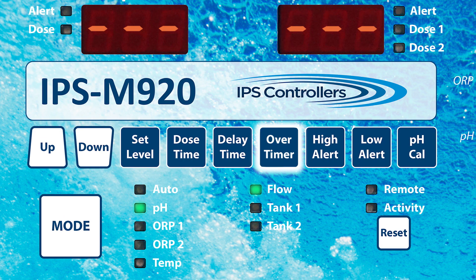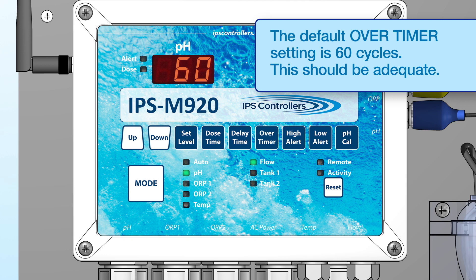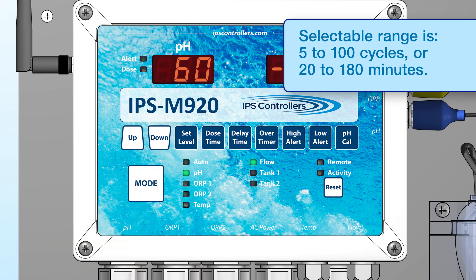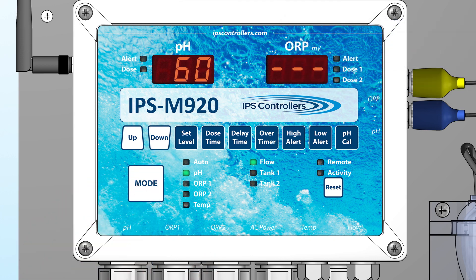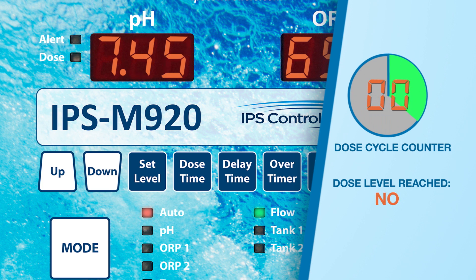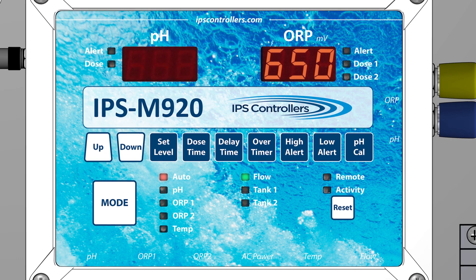The Over Timer is a safety mechanism. Press the Over Timer button to display the current settings; the default setting is 60 cycles. The Over Timer counts the number of cycles that the controller is allowed to dose and delay in order to reach the pH and ORP set levels. If the controller reaches the set levels, the Over Timer resets and normal operation continues. If the set levels are not reached in your chosen number of cycles, the timer will de-energize the chemical relays, and the digital readouts for the pH or ORP will start flashing. The Over Timer will prevent the controller from running any more cycles until the entire system has been reset.